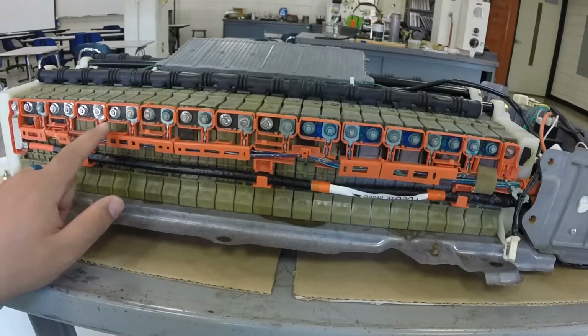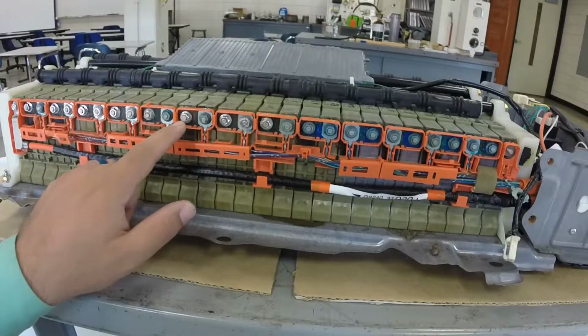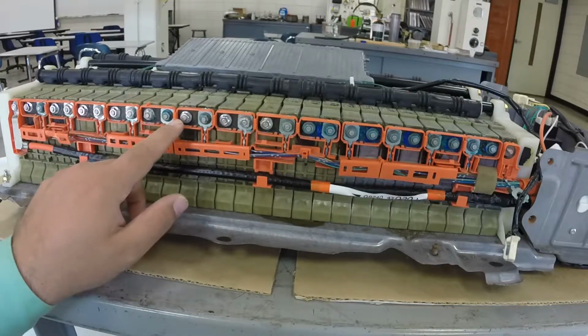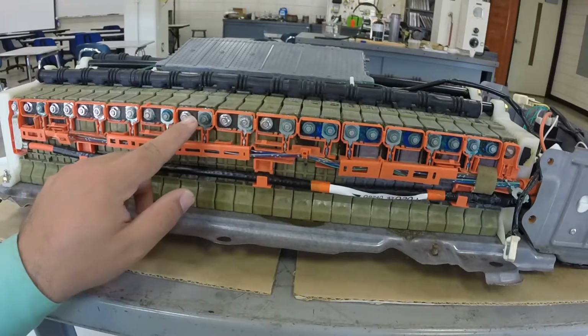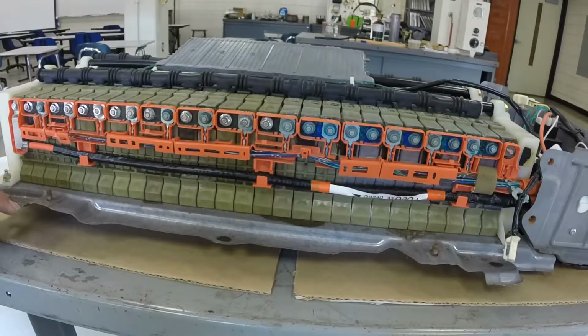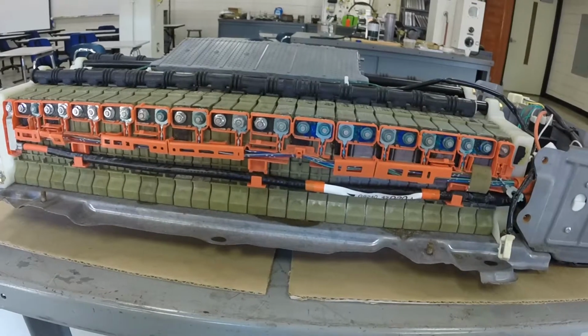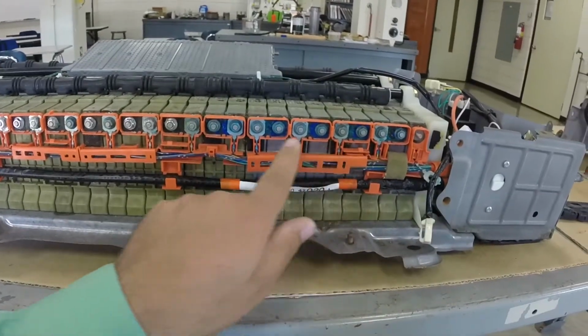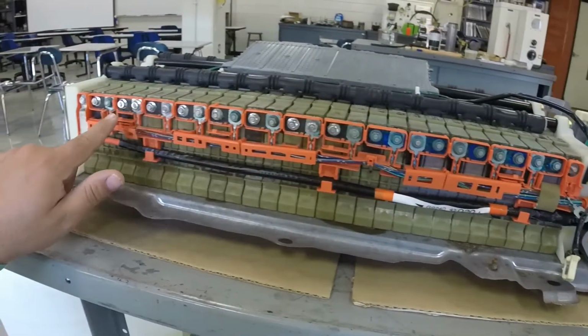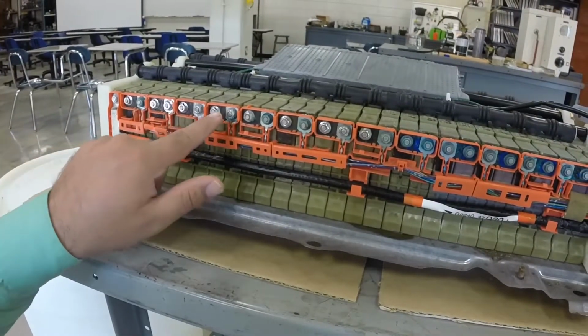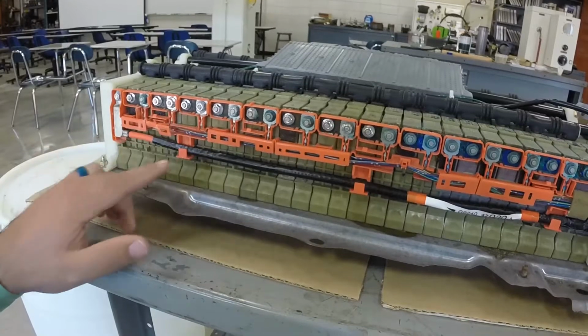If we come down here, we can see that these terminals have copper bus bars going across every other module — these are not connected here, but these are connected here. These copper bus bars do corrode. Notice these over here on this side, these are all very corroded. These are actually pretty corroded as well, you just can't tell because they're darker — they have that dark patina finish on them.